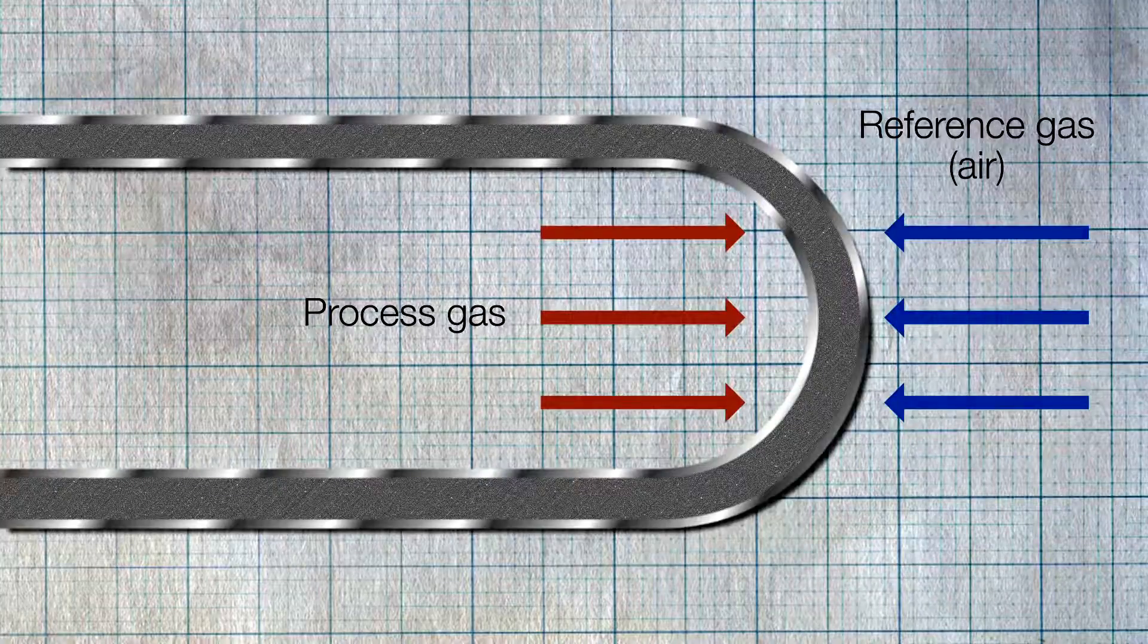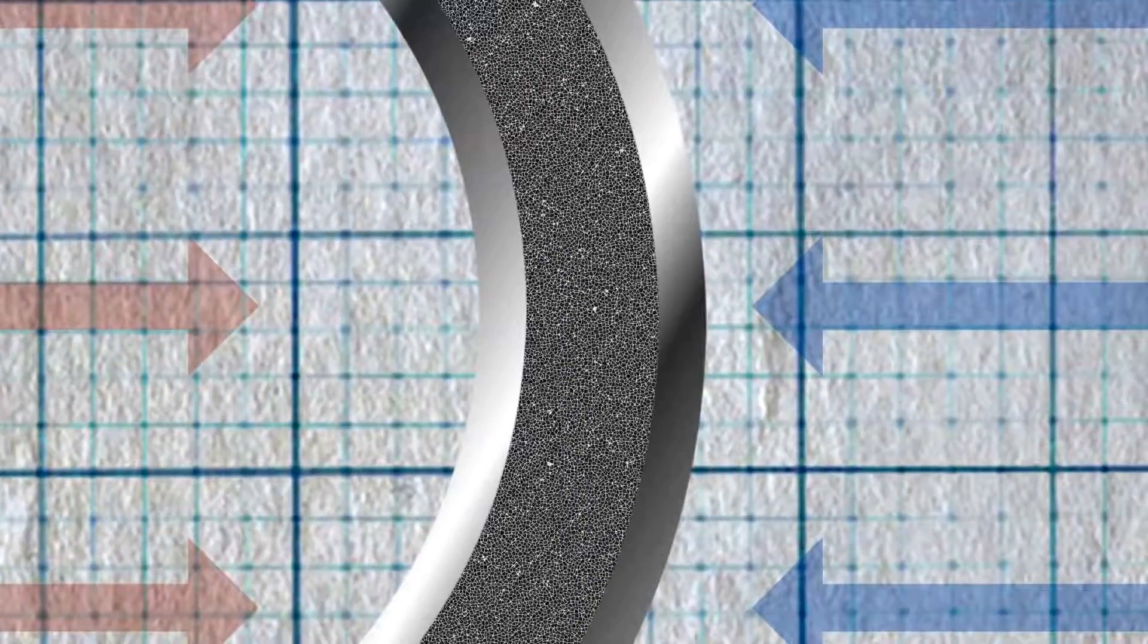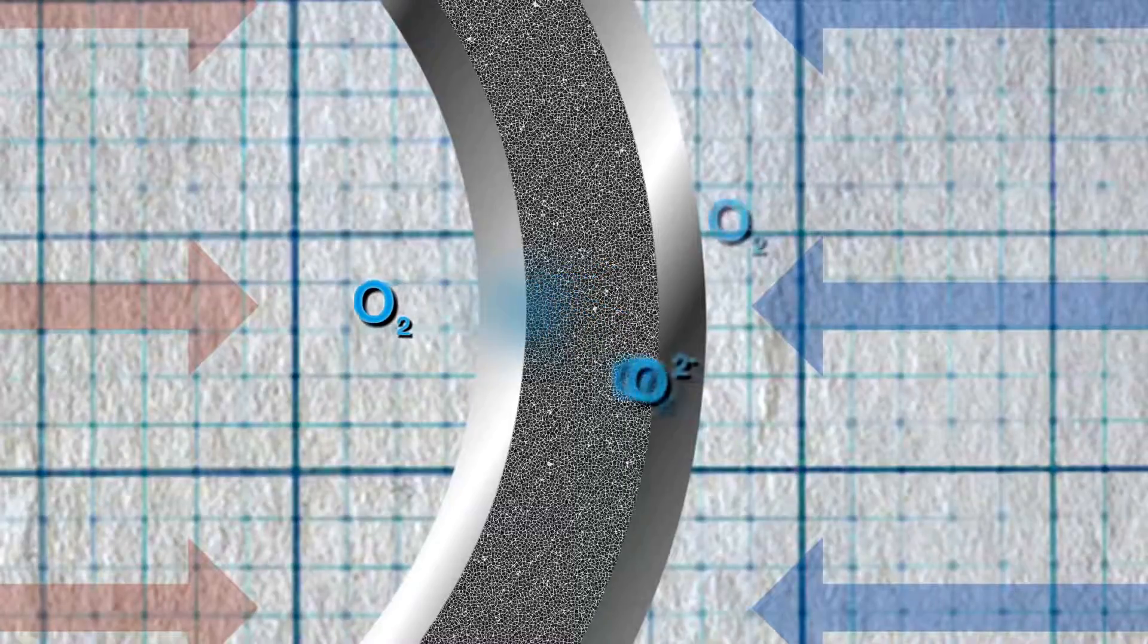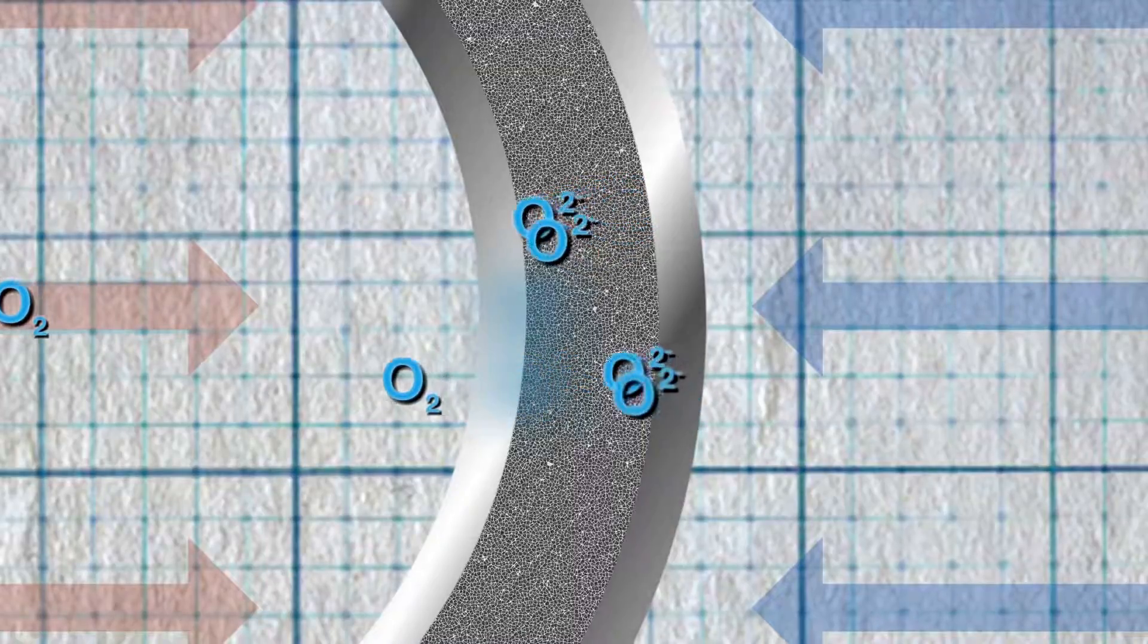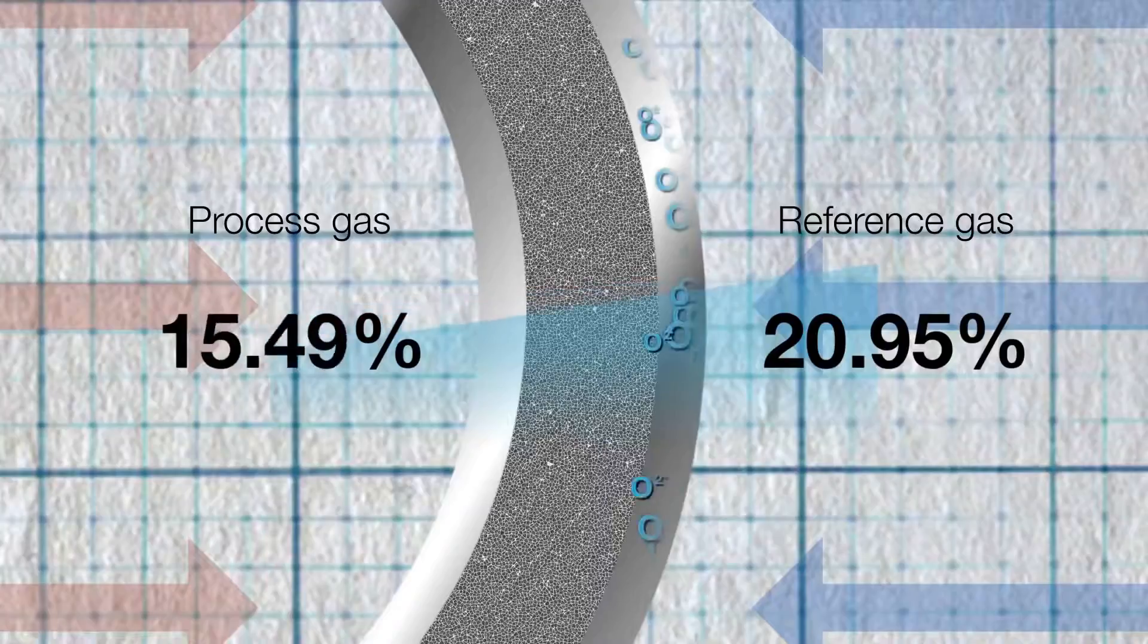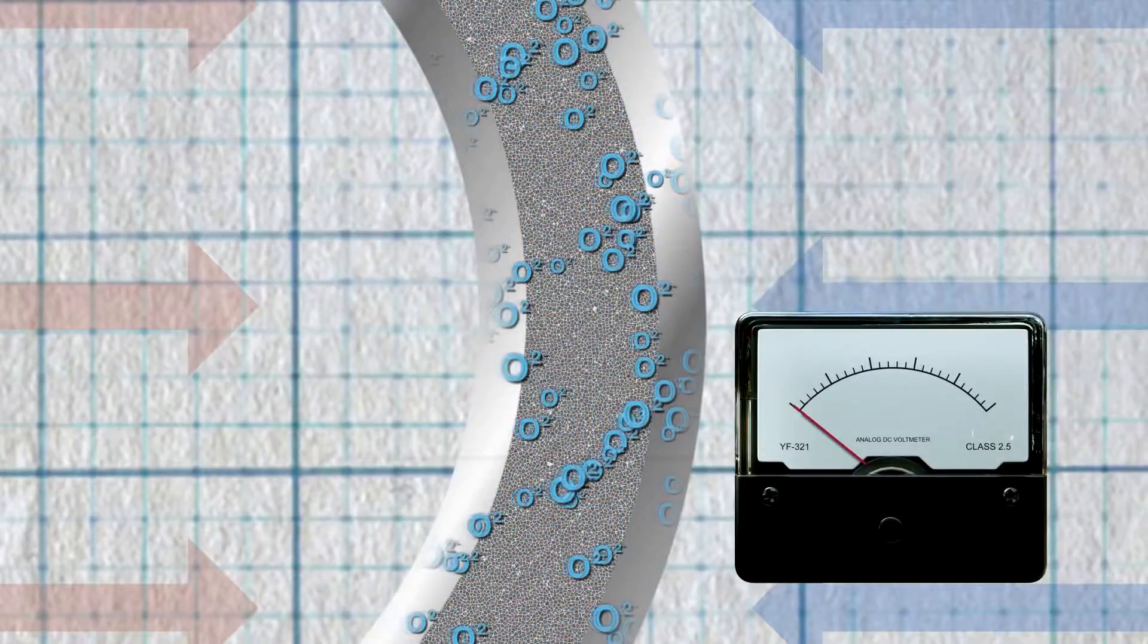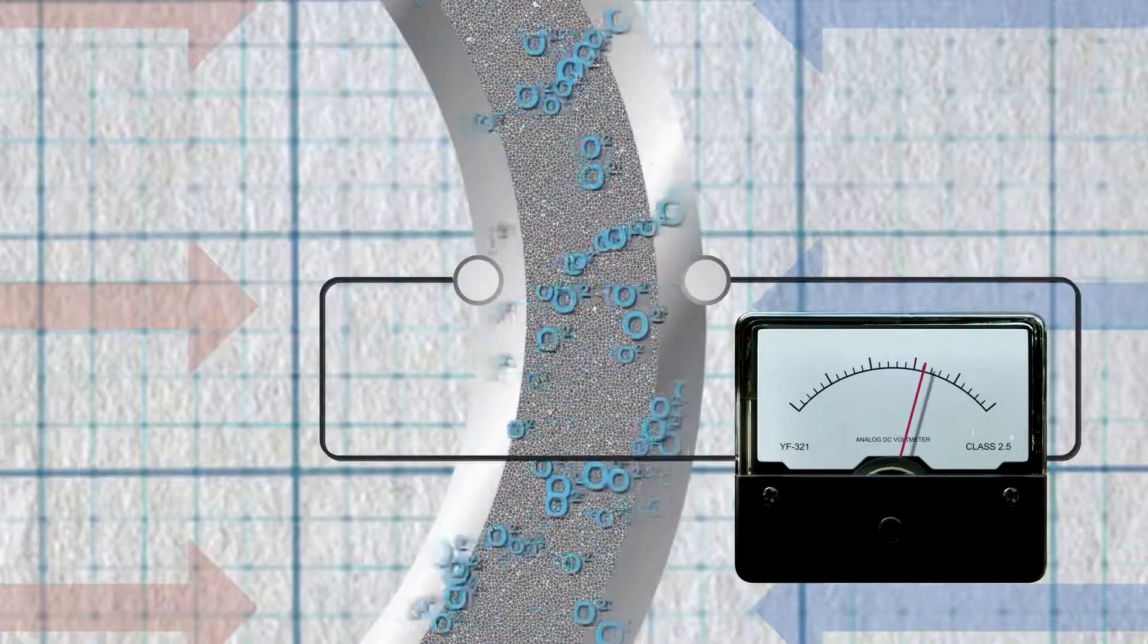When the concentration of oxygen is equal on each side, migration of the oxygen ions through the zirconium is zero. When concentrations differ, migration of the oxygen ions will increase as they try to re-establish equilibrium. The reaction at the two electrodes will differ, generating a corresponding potential difference. Using an appropriate device, this difference can be measured to produce a percentage oxygen concentration reading.